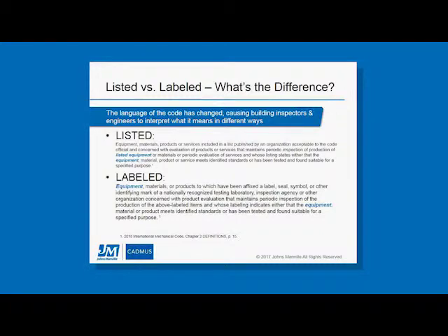The definitions from the International Mechanical Code for listed and labeled are presented on this slide, and I'd like to draw your attention to the bottom half of each definition, where in the case of listing, it states that the equipment, material, product, or service either meets identified standards or has been tested and found suitable for a specified purpose. This same language is listed below for labeling. That gives some options as far as materials in a plenum space: in addition to being either non-combustible or having a 25/50 rating, they need to be listed and labeled according to a third-party entity, such as Underwriters Laboratories or Unitech.